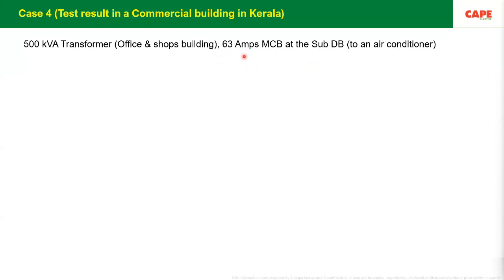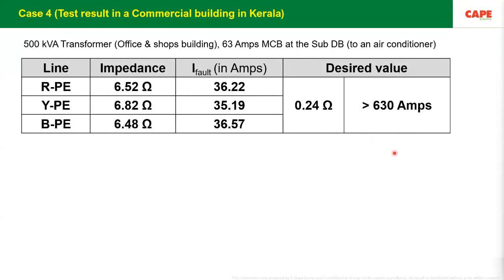It was a 63 amps MCB in a sub distribution board. So the building owner had given an MCB DB to this particular shop, which had a 63 amps MCB. Plus, additionally, there was a 10 amps single pole MCB for some of his light fittings. Now, this gentleman had connected an air conditioner to this 63 amps MCB. He took 4 square mm wire and connected it to the air conditioner. So I tested the terminals of the outgoing of this particular MCB.